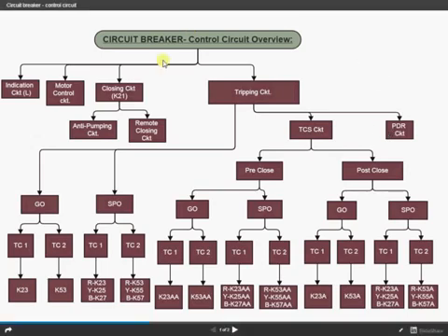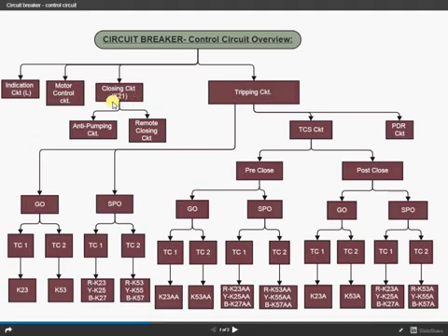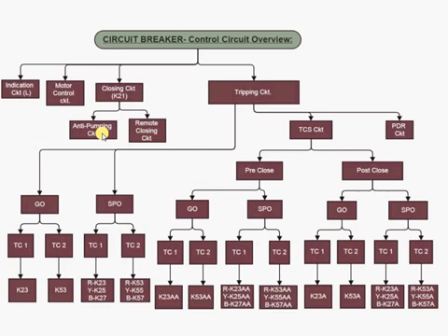Okay. The other circuit is the closing circuit. The closing circuit is used for giving the closing command to the closing coil so that the breaker can be closed. In the closing circuit, the closing positive is given by the ferrule K21. There are two circuits in it, the anti-pumping circuit and the remote closing circuit. Okay. The anti-pumping circuit is like a protection to the closing coil, so that a continuous pulse cannot be extended to the closing coil, it opens that closing circuit.